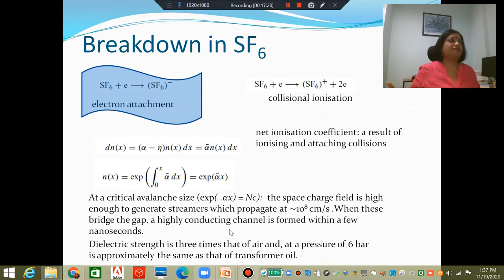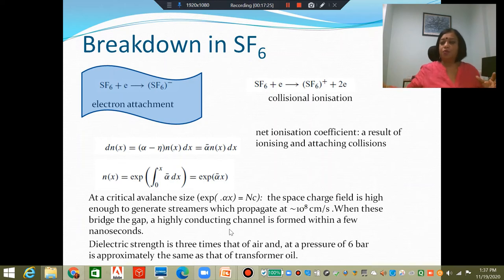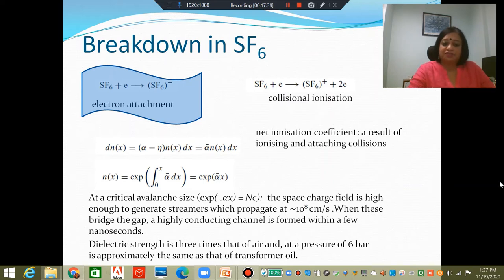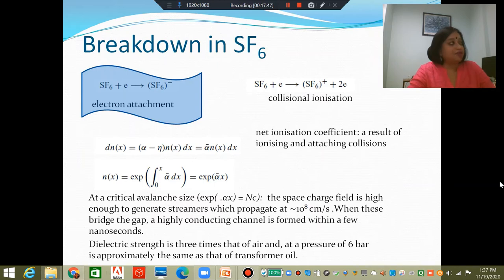First you have electron multiplication as per Townsend's phenomena, and then when sufficient electrons produce accumulated space charge before the entire avalanche reaches the other electrode, photo-ionization becomes possible. When photo-ionization happens, streamer generation occurs and these streamers propagate at a speed of 10^8 cm/s due to photon movement. When streamers bridge the gap, a highly conducting channel is formed and you have complete breakdown. The dielectric strength of SF6 is three times that of air, and at a pressure of six bar, it can be approximately equal to that of transformer oil.